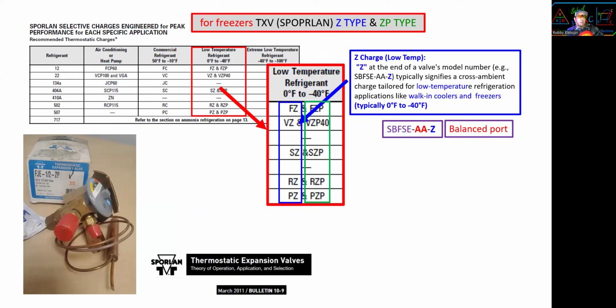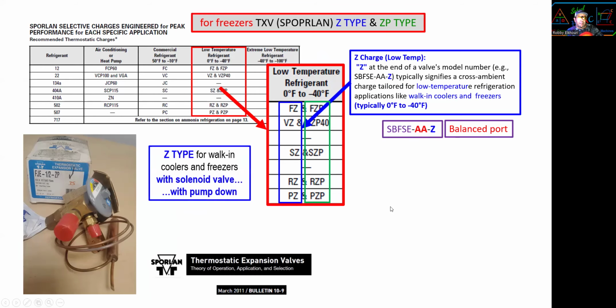Alrighty. We have TXVs for freezers, the Z type and the ZP type. The Z type is for low temperature. This is the charge of the head. When you see Z at the end, it typically signifies cross ambient for low-temperature walk-in coolers and freezers, typically 0°F to -40°F. And now we know AA is for balanced port. Isn't that cool? So this is an AAZ, okay? Balanced port and for freezers. The Z is for walk-in freezers and coolers with solenoid valve pump down.